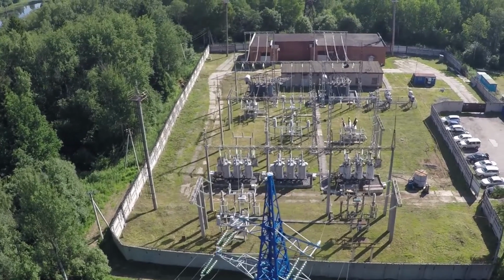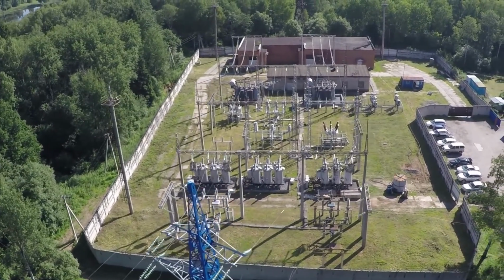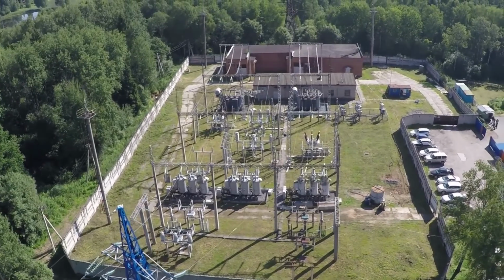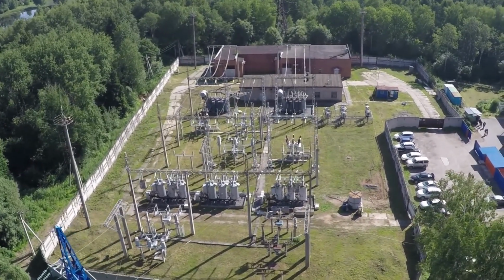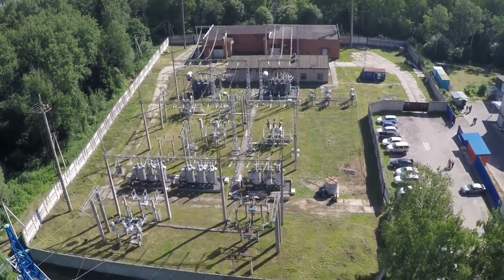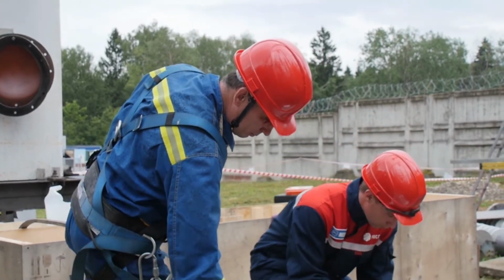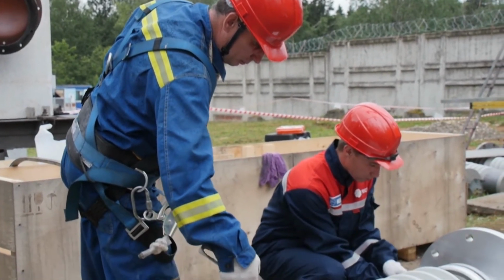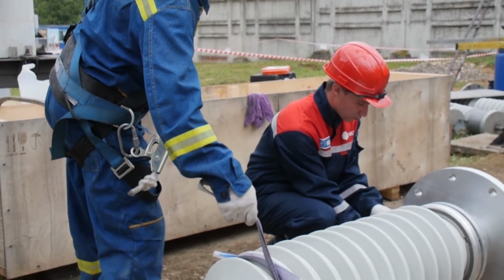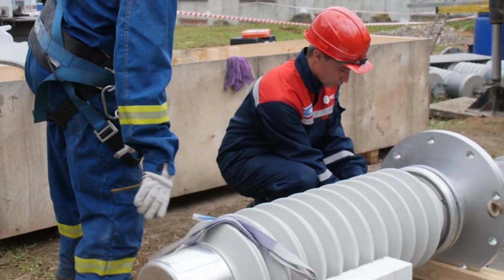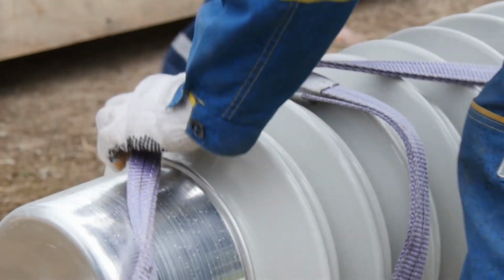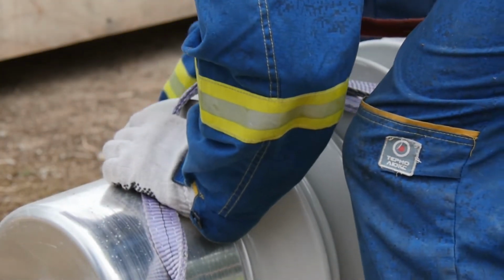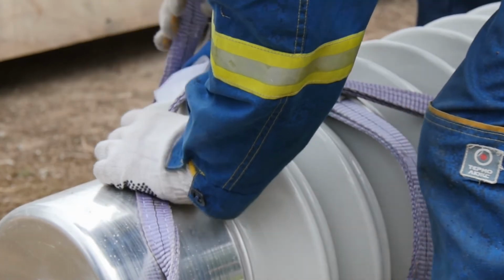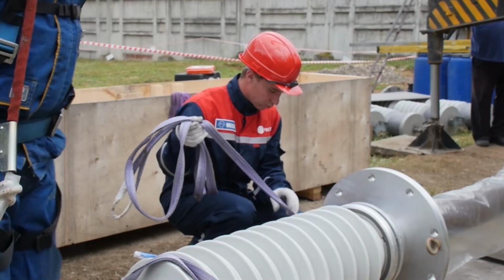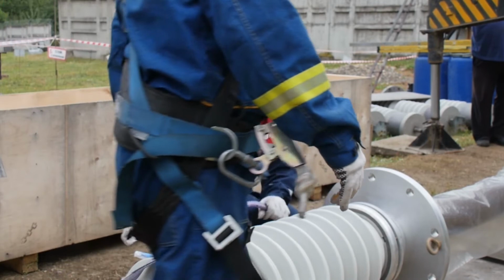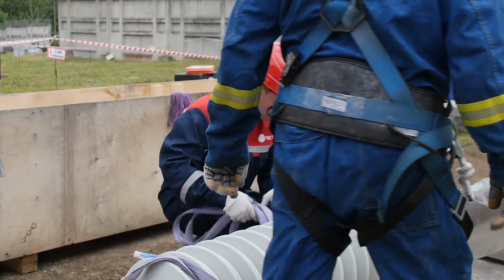Set the bushing vertically. This procedure is especially vital as there is a risk of damaging the bushing bottom. However, if specific rules are followed, this operation will be easy to perform. To tie the bushings up, lead 2 soft slings along the porcelain housing up to the coupling. Tie these slings with an additional sling between the second and the 5th large sheds of the porcelain housing. Tie up the slings using the handling appliances on the coupling, lugs or eye bolts.